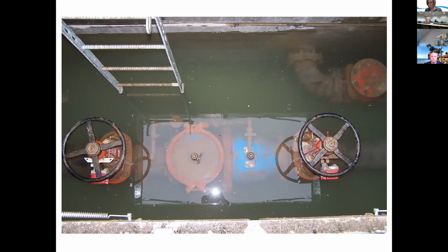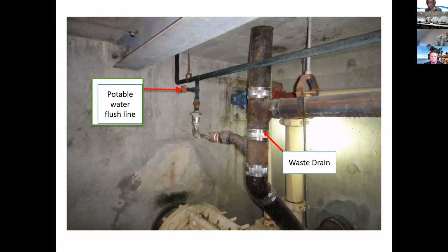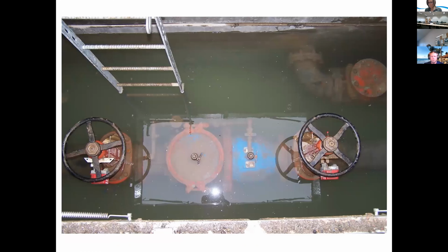You shouldn't be relying on a sump pump. But there are tons and tons of these out there where you go out to test the backflow assembly and you have to pump out the vault in order to get to it. It's just not safe conditions. It's going to lower the life expectancy of your backflow assembly. Again, if there's any kind of opening anywhere, even just a small crack, it can actually pull water in as water's flowing through the backflow assembly.